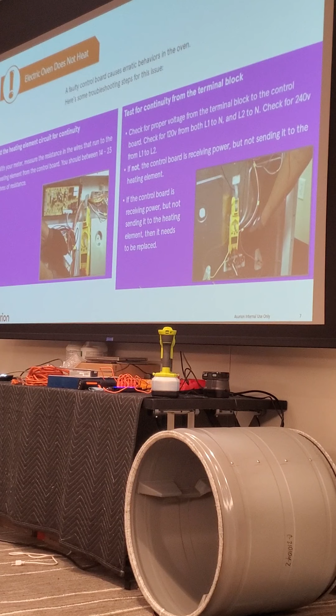So test the heating element circuit for continuity. Not like the way they did it here - you separate the one wire and you can test your amperage here, but then you can hang your meter up there and test for continuity just by testing your wires to the heating element. You can go right straight to the heating element and test it all the way through, and get your ohms.